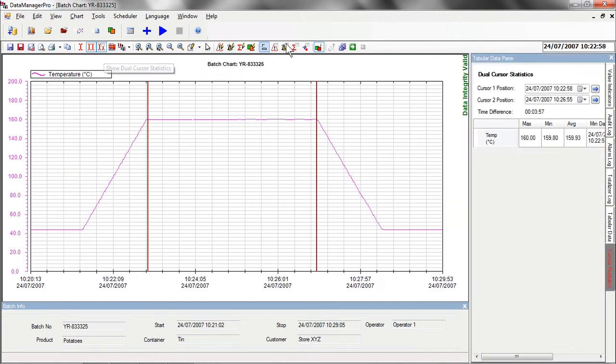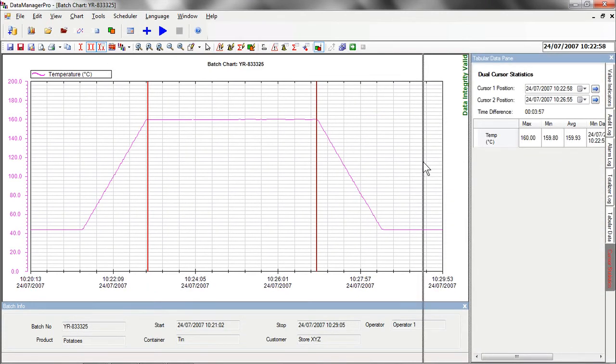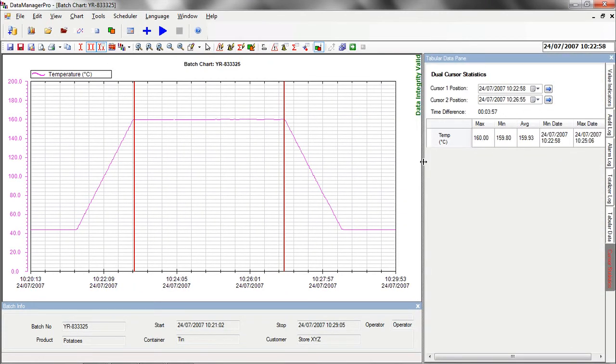We can then bring up the statistics for the batch by selecting the Dual Cursor Statistics function. From these statistics, we can see that the batch was cooked for 3 minutes and 57 seconds at a minimum temperature of 159.8 degrees.